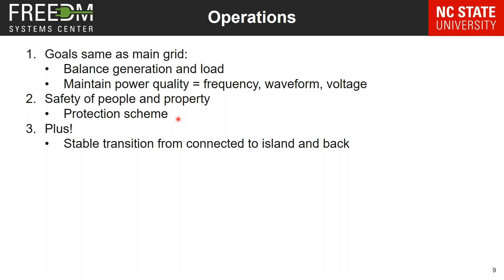While in operating mode, you're either grid connected or islanded, which adds additional complexity. While grid connected, your microgrid can participate in demand response programs, receiving a signal from the utility saying loads are increasing and asking you to decrease your load; participants are usually compensated for reducing power demand during that time. Or if you have excess power, there's potential to sell it back to the utility, though only certain utilities can handle that or have regulations allowing it. You can also participate in frequency response programs and provide voltage support, again receiving signals from the grid, and the list goes on.